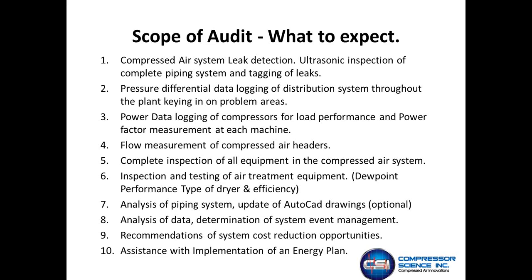Flow measurement of compressed air headers, I think, is critical, especially with upper range modulation compressors and different compressor control schemes. If you're simply taking an amp and a pressure reading and trying to correlate that into a flow measurement using a software system, I've seen a lot of systems that have failed because of that. You really have to take the discharge flow measurement from the compressor room and correlate that with the amps to get a true kilowatt per 100 CFM specific power.